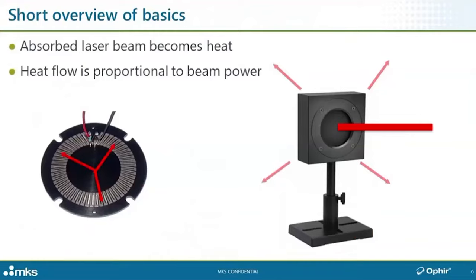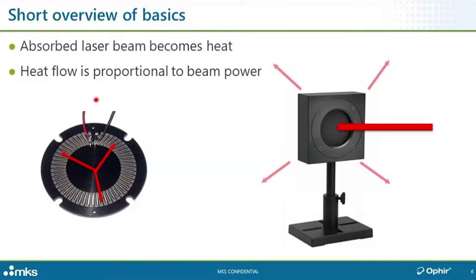The very basic review of how these high power laser sensors work: we're absorbing the laser beam, the absorbed optical power is turned into heat, and we measure the flow of heat. Basically, we have a metal disc on which we have a heat detector — a thermopile. In this image we're looking at the inner side of such a disc; the laser beam would be coming towards you. The absorbed light turns into heat which spreads radially outward, and this heat flow detector measures the heat flow and turns it into an electrical signal going out to the other half of the measurement instrument — the meter, display, controller, or reader.